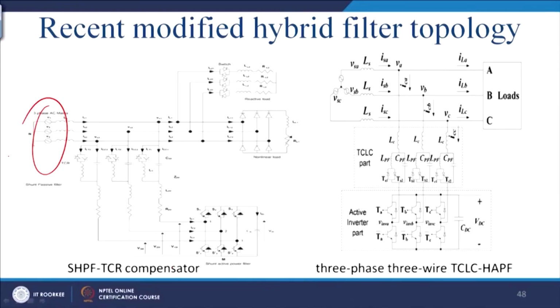Essentially you have a source, and thereafter you put FACTS devices like the TCR, the thyristor controlled reactor. The value of the inductance will depend on the firing angle of these thyristors. Please refer to my FACTS course, where the details have been covered. The inductor value can be modified by changing the firing of the thyristor. These combinations also offer reactive power compensation, which is the task of FACTS devices, and apart from that they give you the shunt active power filter.